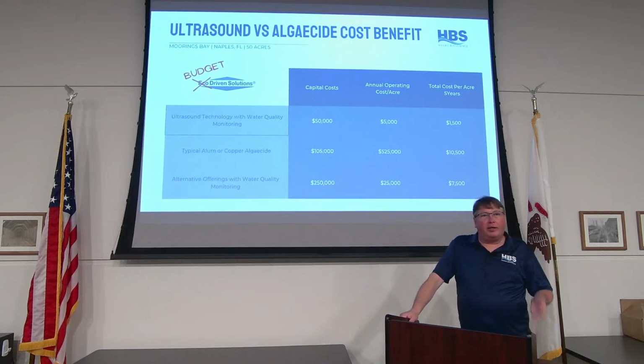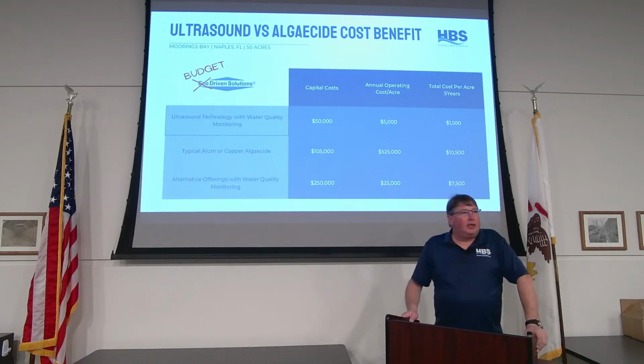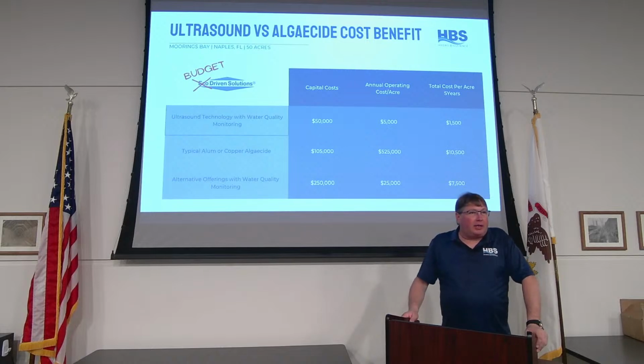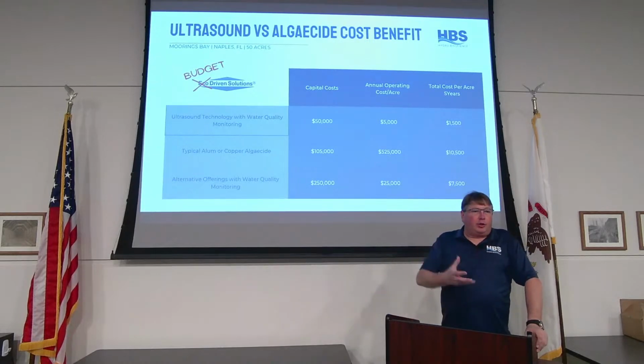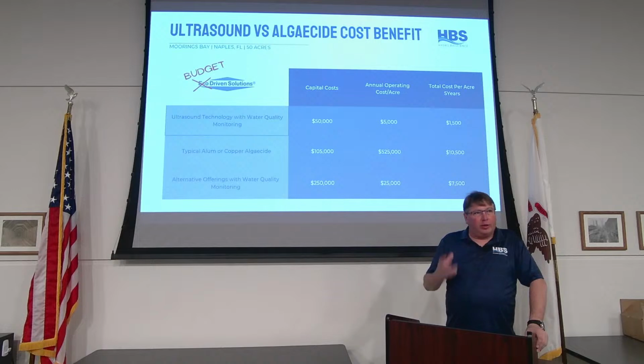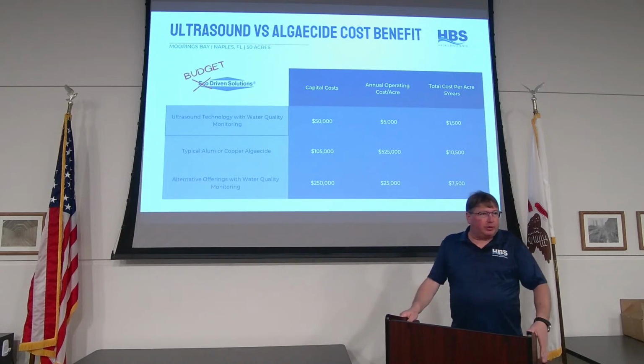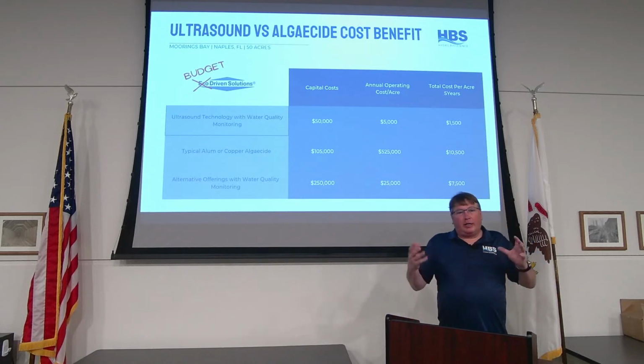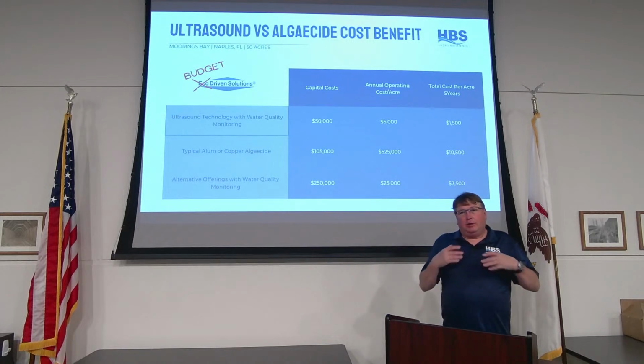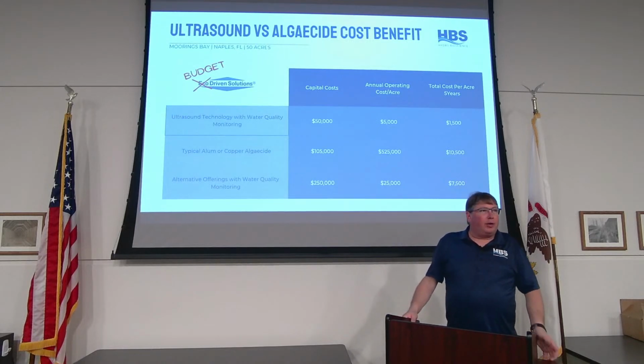It's the fully potted system. So if something does happen, say it gets dropped, it gets cracked, something like that, the circuitry and the transducer crystals, we use a piezo crystal on the inside, are actually fully potted. So you're not going to leak any water in there. You're not going to create a problem.